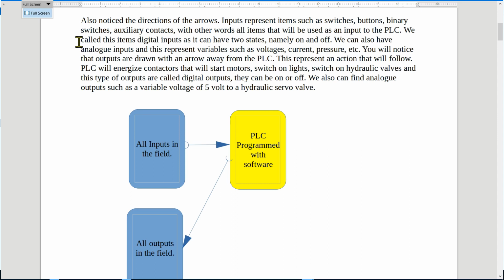But when we talk about inputs, we can also have analog inputs, and this represents variables such as voltage, current, pressure, etc. You will notice that outputs are drawn with an arrow away from the PLC. That represents an action that will follow. Now, the PLC will energize contactors that will start motors, switch on lights, switch on hydraulic valves, and this type of output is called a digital output. And they can also be on or off. And that's why it's called a digital output.